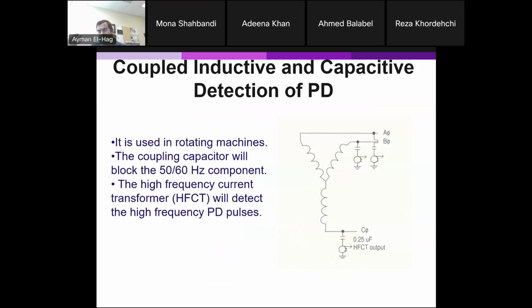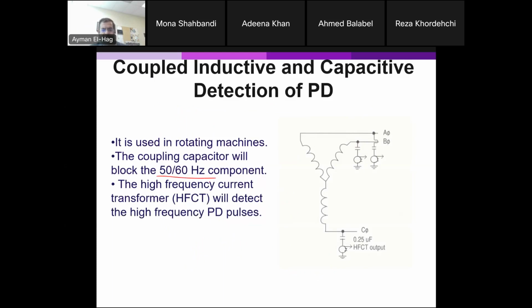Now, to help improve this a little bit, especially when we use it in rotating machines, we use a coupling capacitor. Okay, so these are coupling capacitors here. You put them in the way between the leads and the current transformers. And why is that? You want to block the 50-60 hertz components, okay? And you only want to keep the high frequency. So instead of directly connecting it, you use those coupling capacitors to filter out the 50-60 hertz and keep the high frequency.